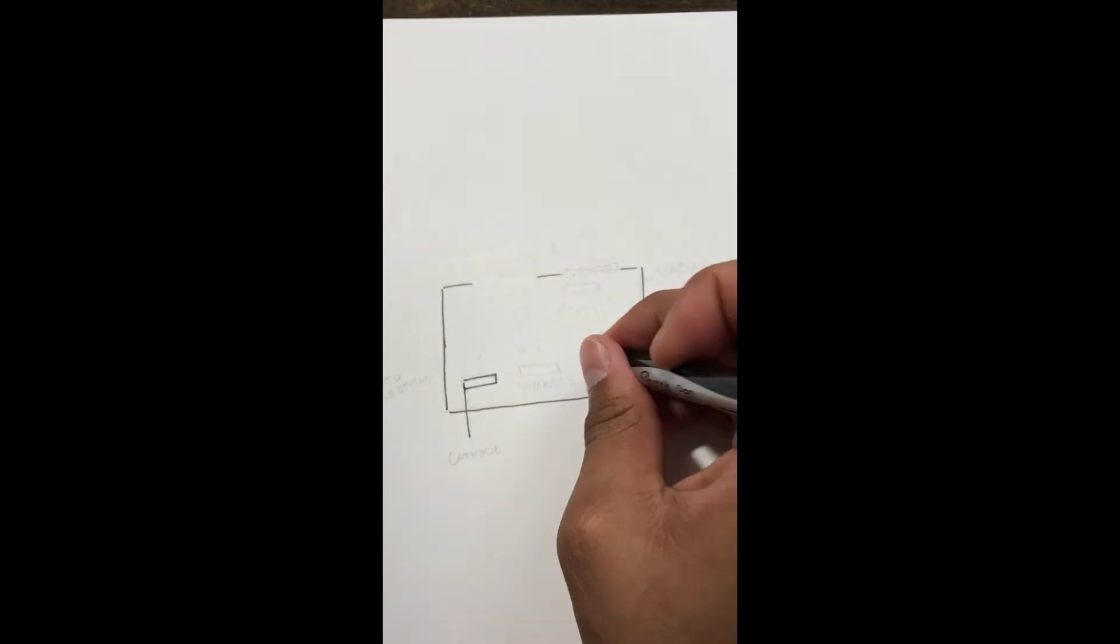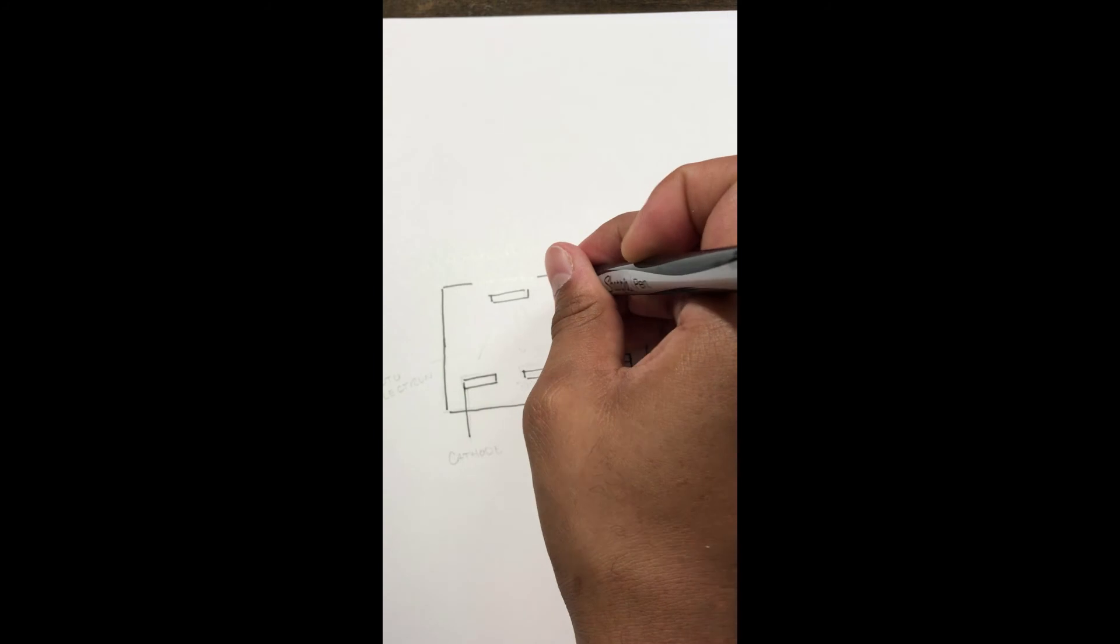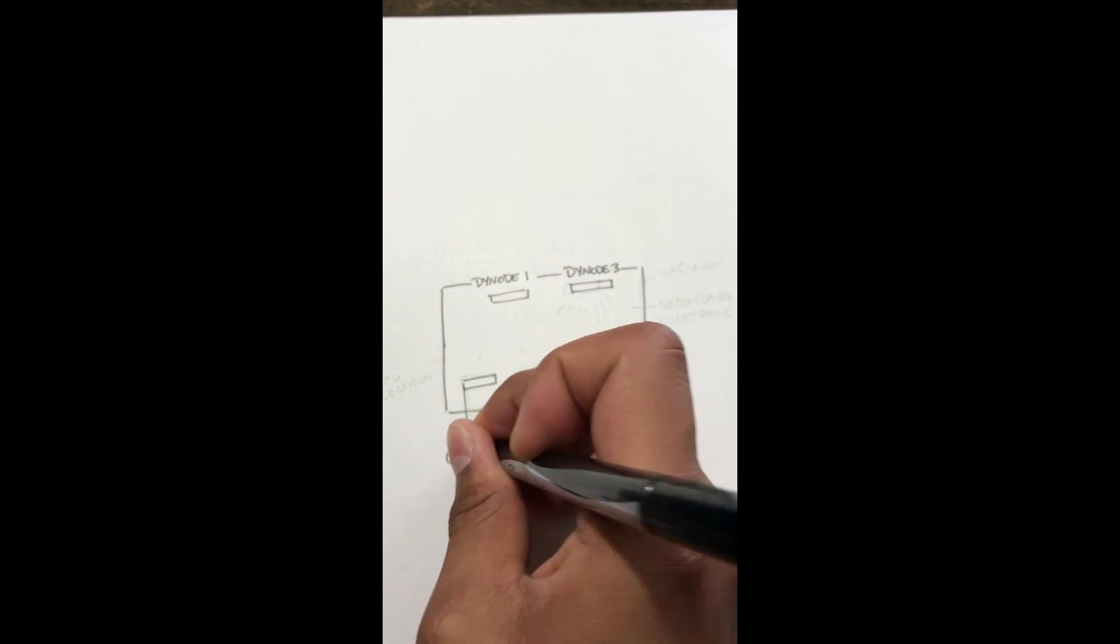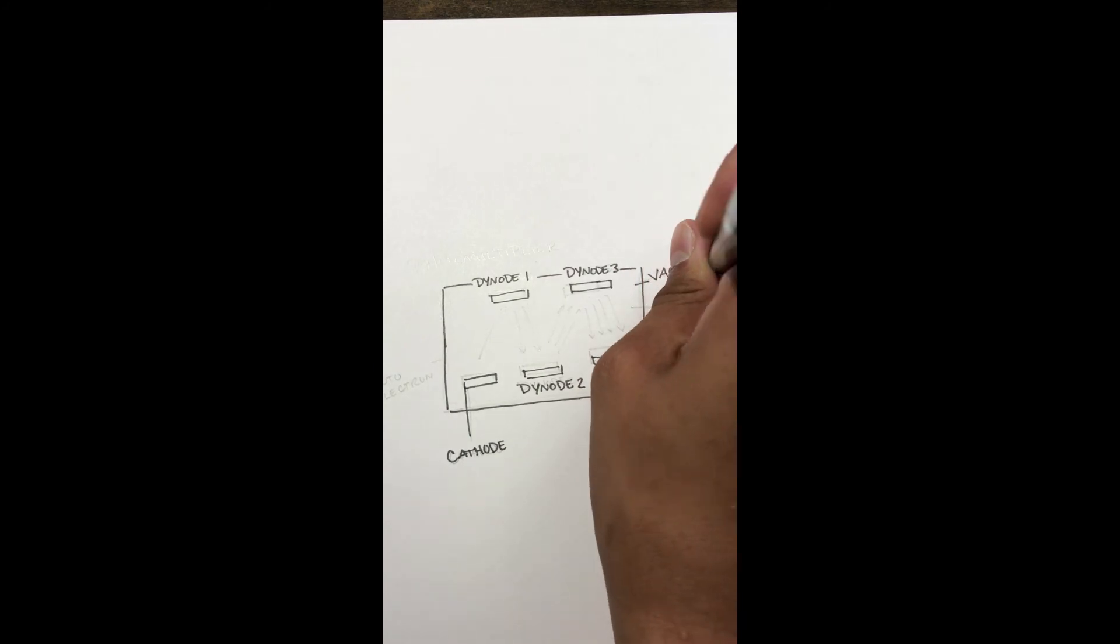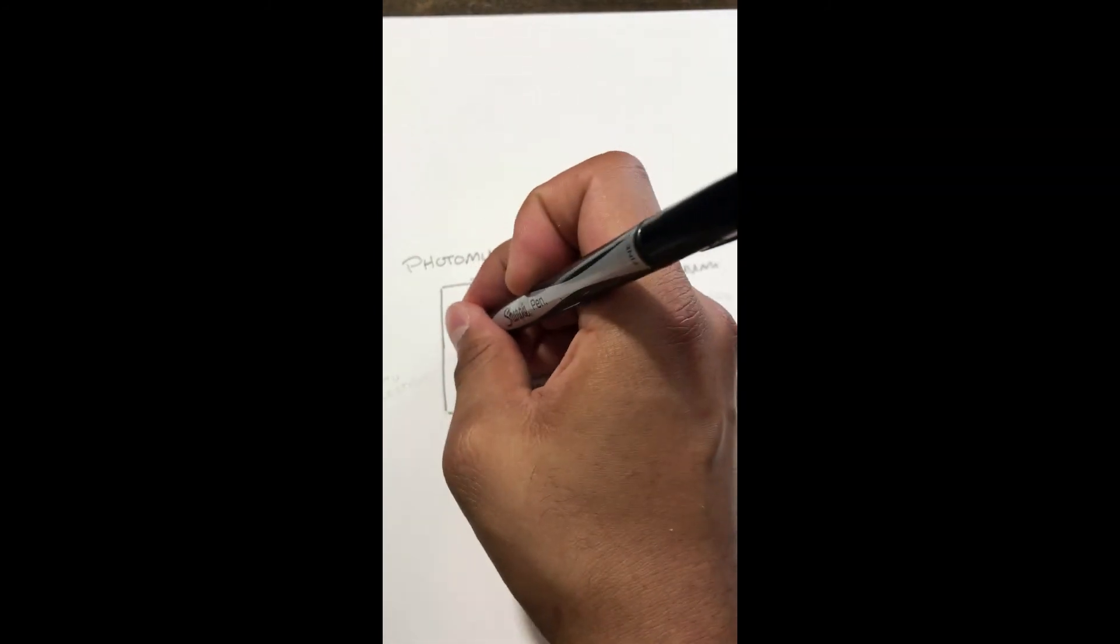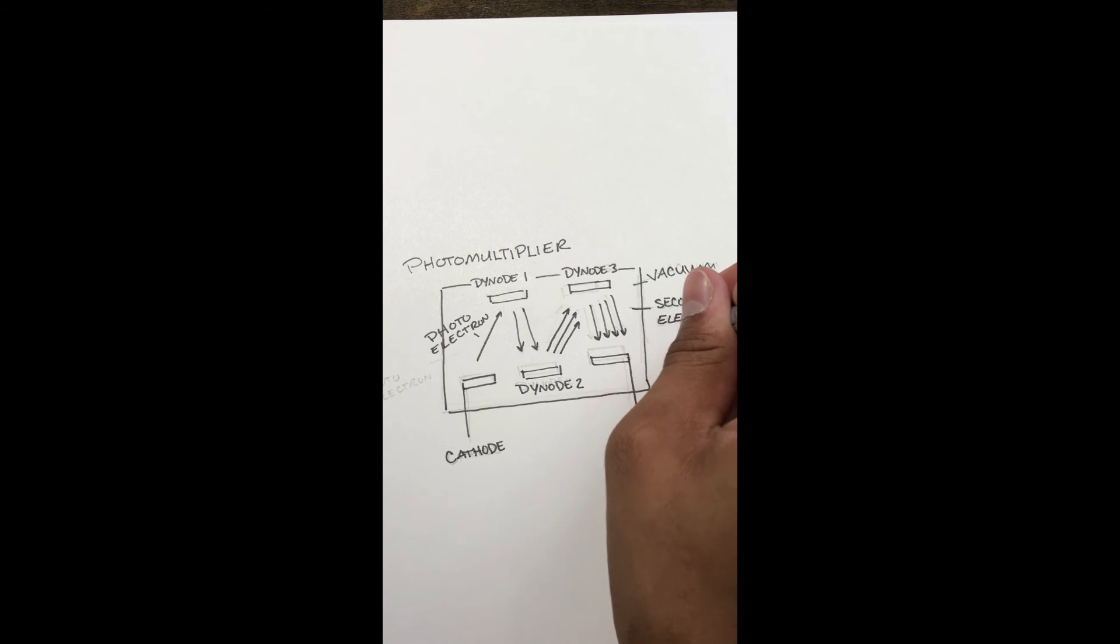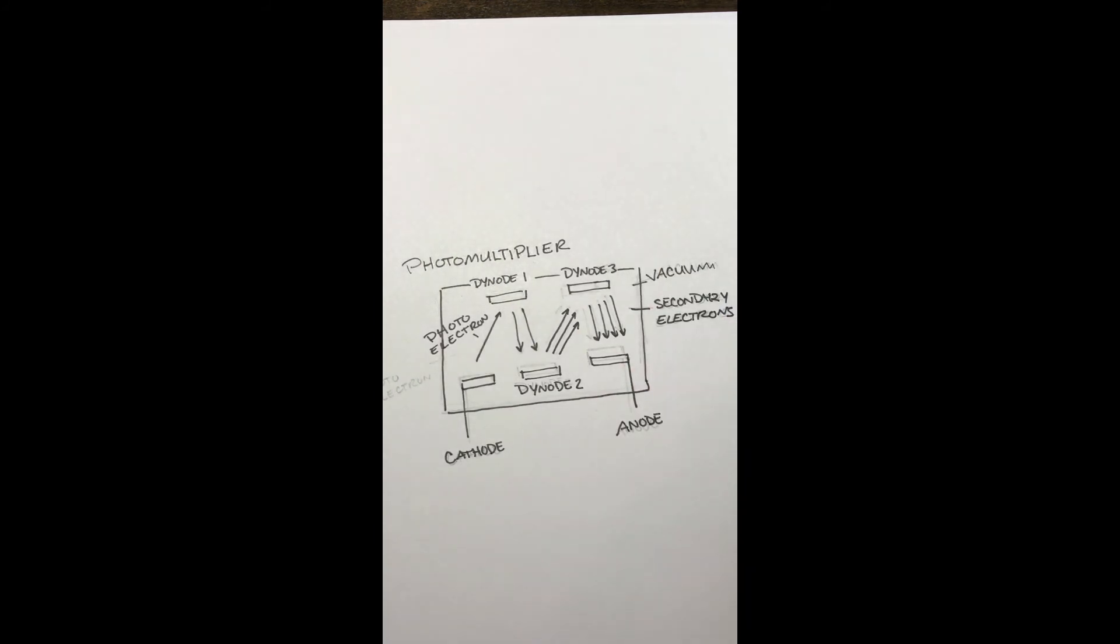Photomultipliers can amplify the current because of secondary emitting sources known as dynodes. These are arranged such that electrons from each dynode go to the next dynode in series. So as one electron is emitted from the cathode and accelerated by an applied voltage, its impact on the first dynode causes the emission of many secondary electrons and their impact on the next dynode multiplies the number of emitted electrons even more, leading to an increase in current.